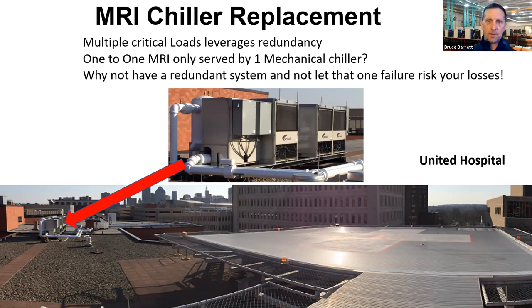So in the cold Minnesota winters, when they're trying to deliver 53 degree water to the MRI machines, we're not running any compressors for about 4.5-5 months. We're not beating those compressors up under low ambient conditions. You'll see on the right-hand side, that is a helipad. There's rocks on the roof. One of our coils took a rock through it.